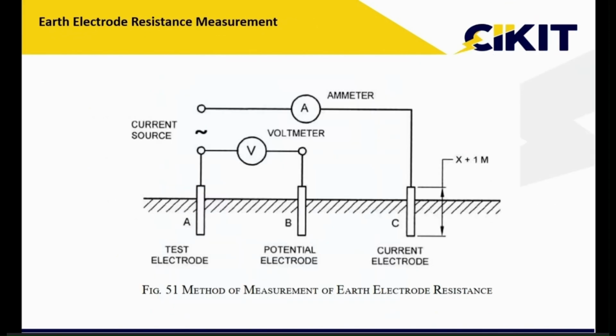As I mentioned, the earthing resistance associated with the earthing is electrolytic in nature. It can be measured by injecting the current through the soil only. So we will be injecting the current between the current source and the test electrode, and we will be measuring the voltage drop between the potential electrode and the test electrode. The ratio of voltage to current will be the resistance. That is how we will be measuring the resistance value.